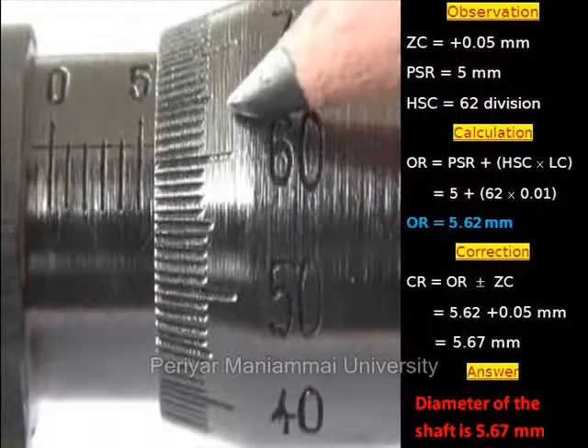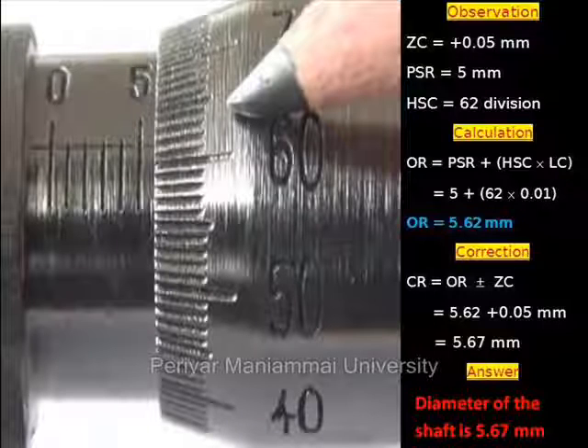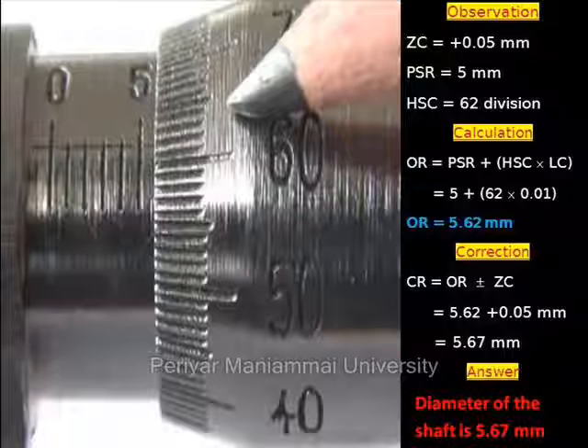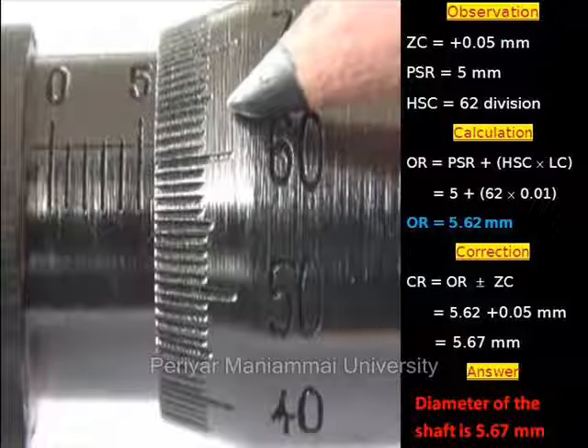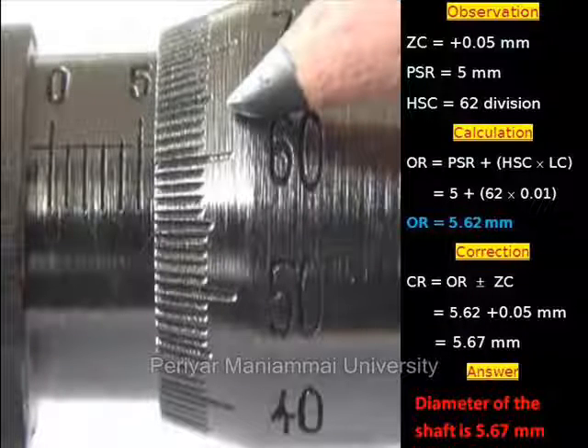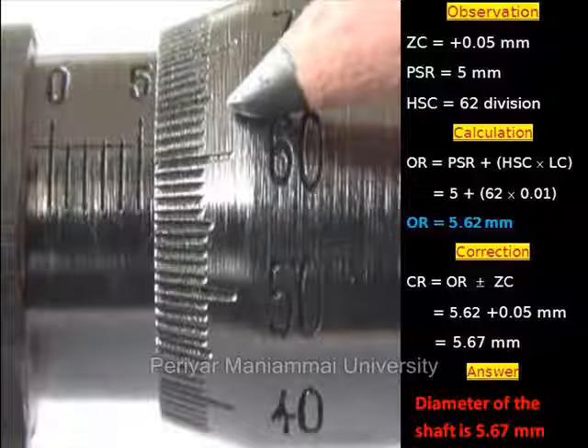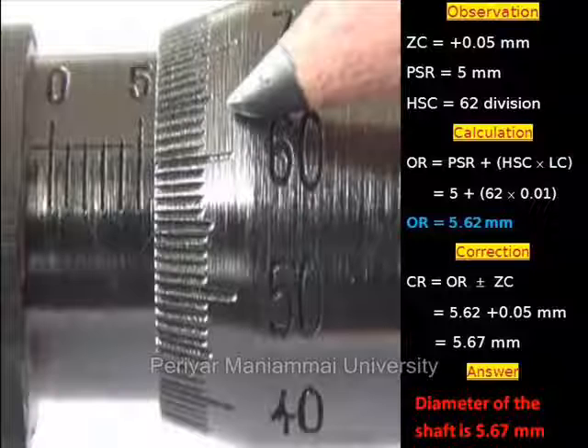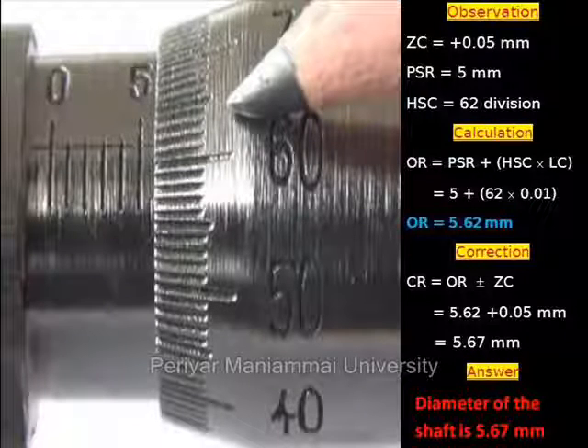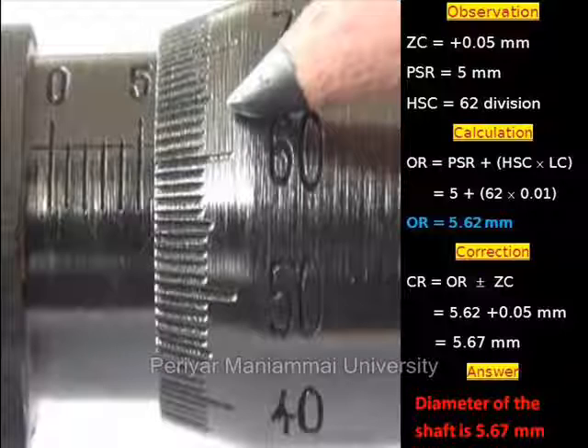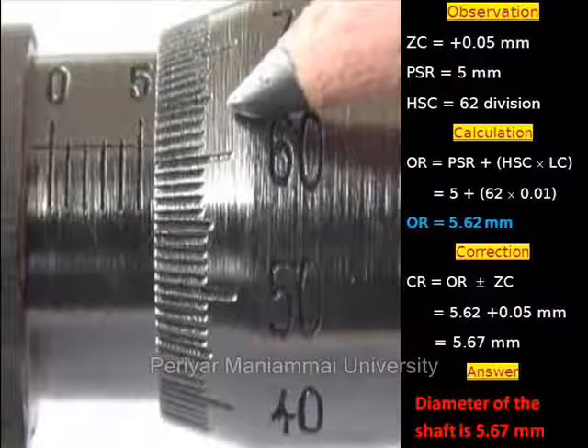So the observations are pitch scale reading 5 mm and head scale coincidence 62 divisions. So we can substitute the value and we will get the observed reading 5.62 millimeter and after correction we get 5.67 millimeter. So the diameter of the given shaft is 5.67 millimeter.